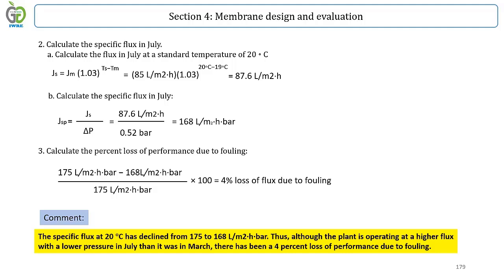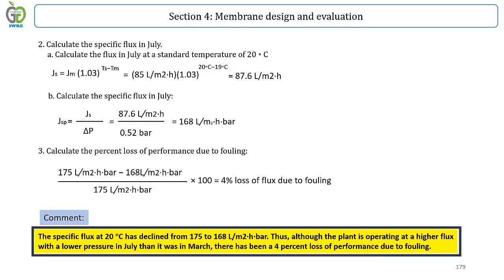After calculations, as a consequence, the specific flux at 20 degrees Celsius has declined from 175 to 168 liters per square meter in hour in bar. Thus, although the plant is operating at a higher flux with lower pressure in July than it was in March, there has been a four percent loss of performance due to fouling.